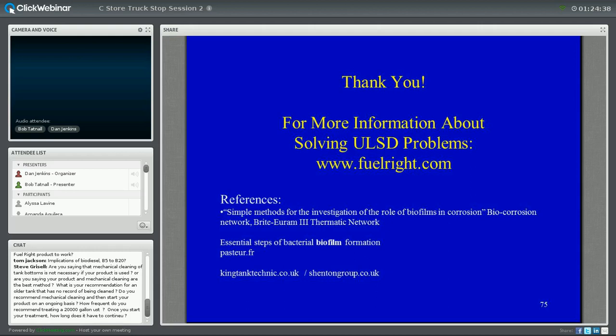Now, there is a problem with biodiesel that I may go to my grave being the only person that admits, because the people pushing biodiesel turn a deaf ear to this, and I don't blame them, because there's a lot of upside to biodiesel, and I love biodiesel for a lot of reasons. But if there's water and biological contamination in a number 2 fuel system with biodiesel, you get a black, sticky substance that starts to form in weeks, not years. It's like soft tar, sticky, and it is so hard to clean off of things, and it can really mess up a system.